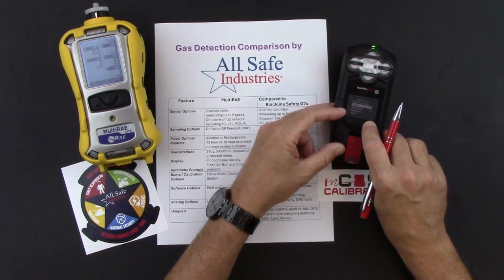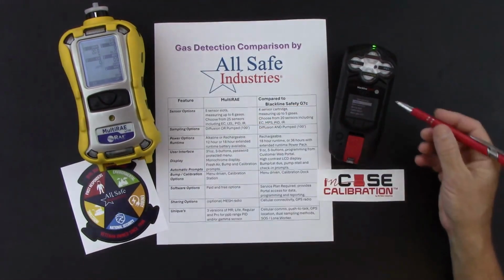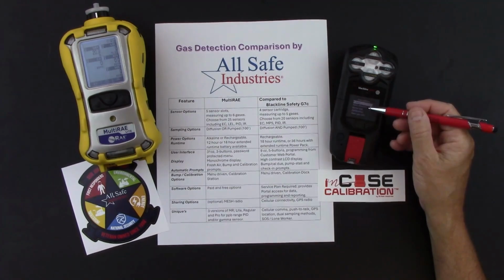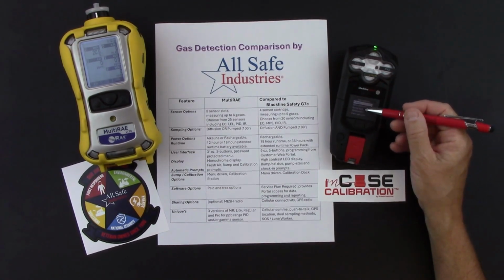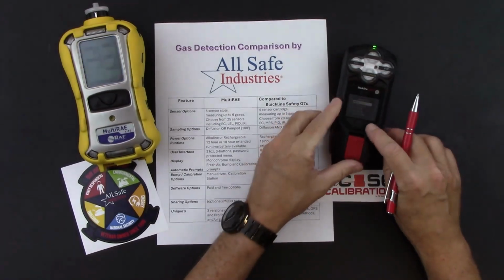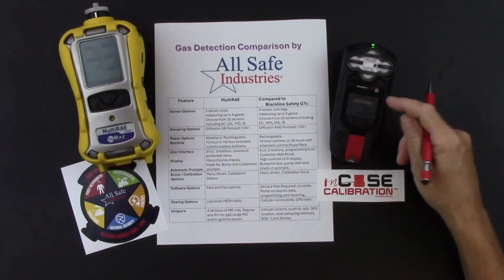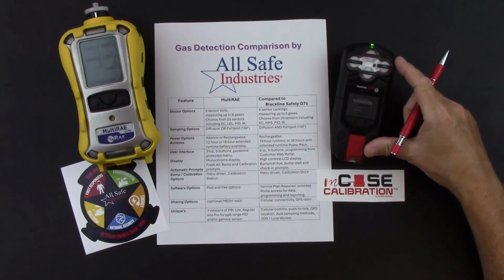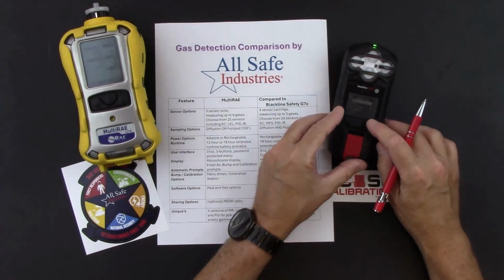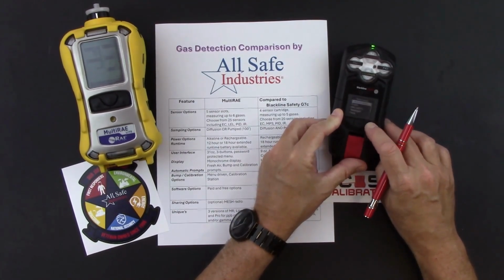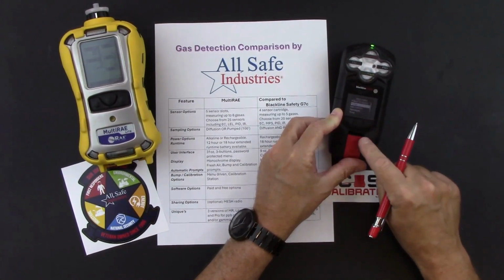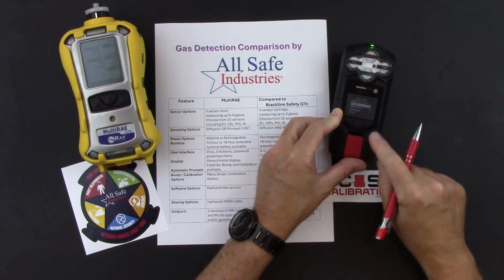I want to show you really quick for gas options, and there's my choices. I can zero my sensors again, I can run a bump test, I can run a calibration, and I can view gas info. So as I mentioned before, the G7c boots up into diffusion mode, and I have this mode menu here that I can use to select a different mode, including turning on the pump.